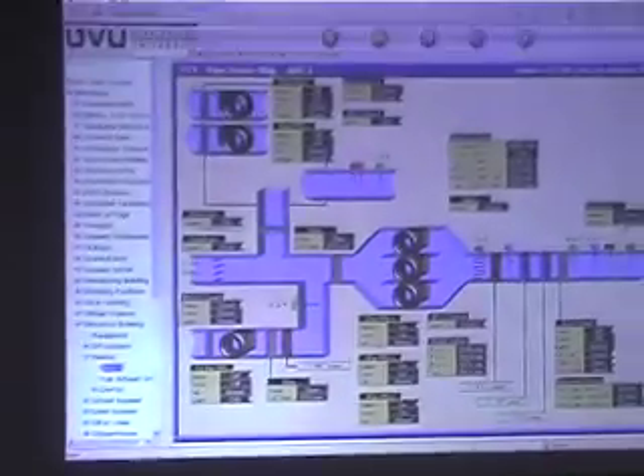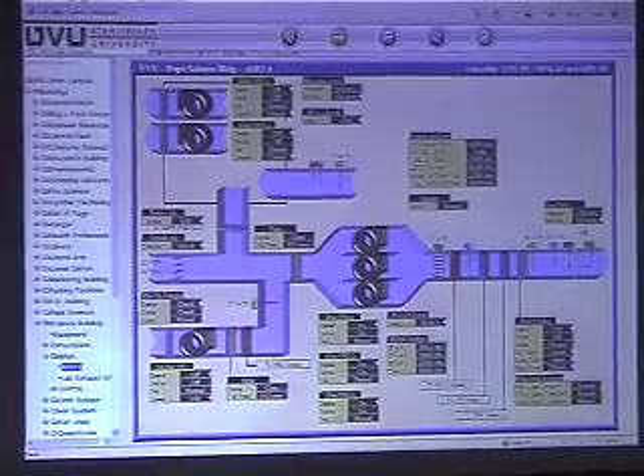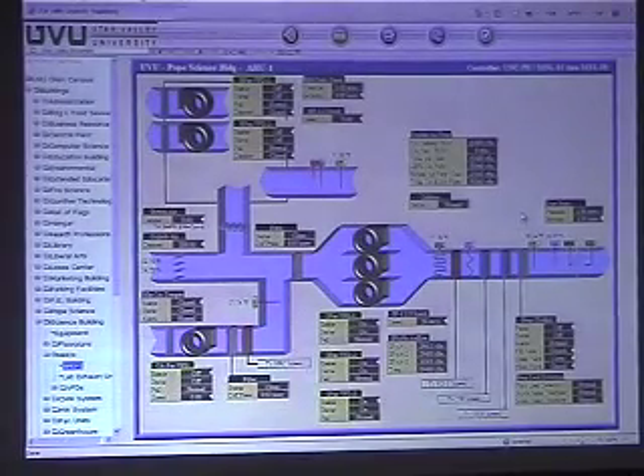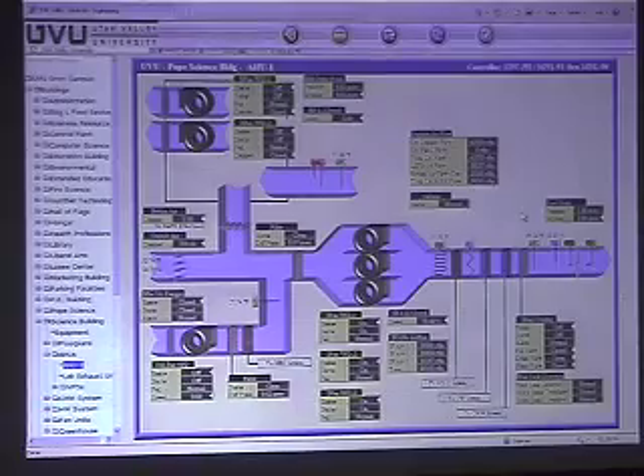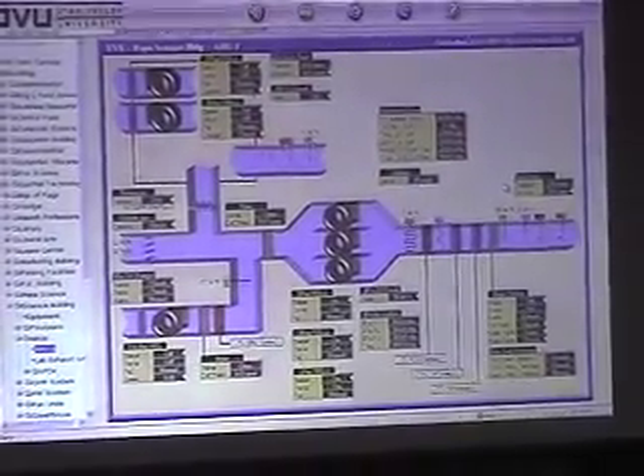Air handler's controlling off the speed of the fans, controlling off duct static pressure. So with the balancer determined that we need 2 inches, but I'll be adding a reset to this graphic screen because we actually need 2.5 when the large lecture hall on level 1 is calling for full cooling in that space. It needs more static pressure to get the airflow. But otherwise, when those cut back or when there's nothing going on in there, then the air handler is satisfied with 2 inches.